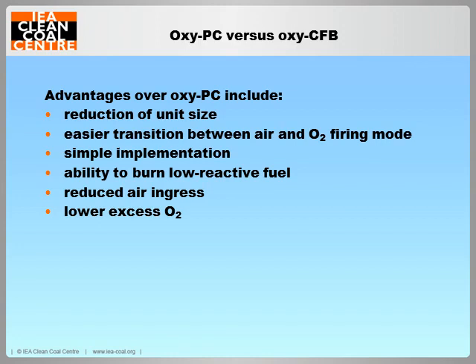The strong mixing in the Oxy-CFB furnace and the long residence time due to the recirculation of solids allow a good carbon burnout, and this clearly suits the low reactive fuels. Large part of the Oxy-CFB furnace operates at positive pressure, so the air in leakage is low, and it uses low excess oxygen, resulting in increased CO2 recovery and a reduced energy penalty.